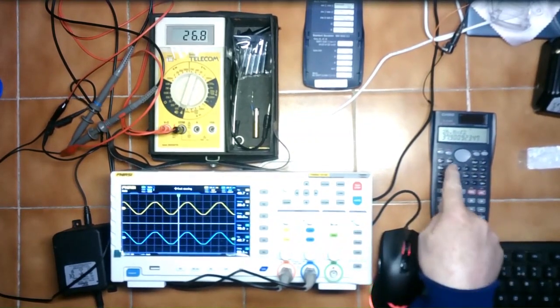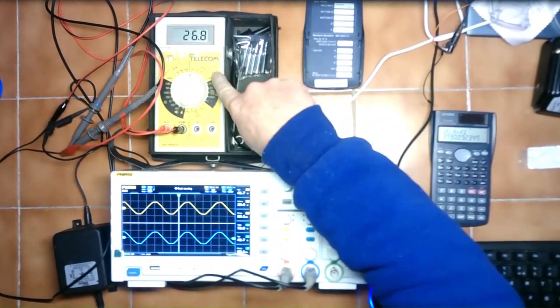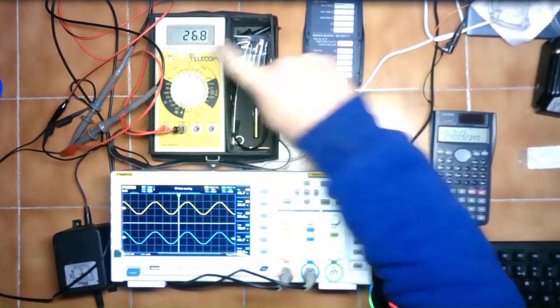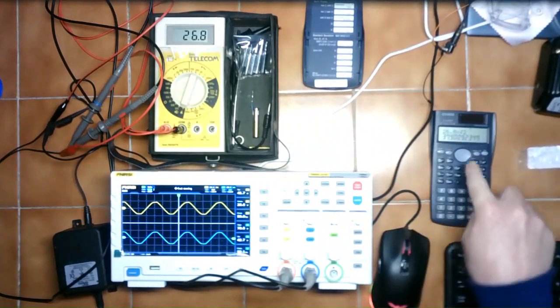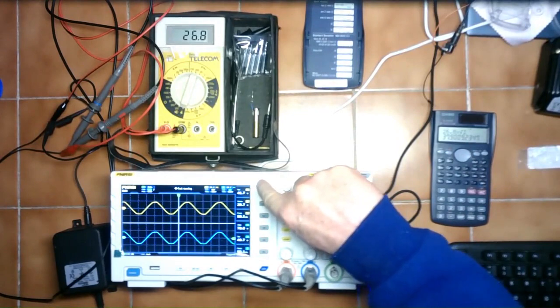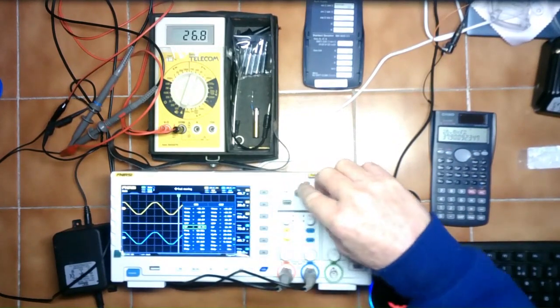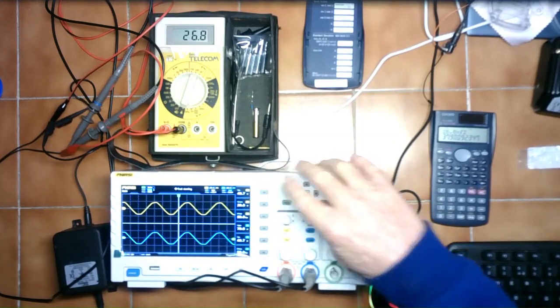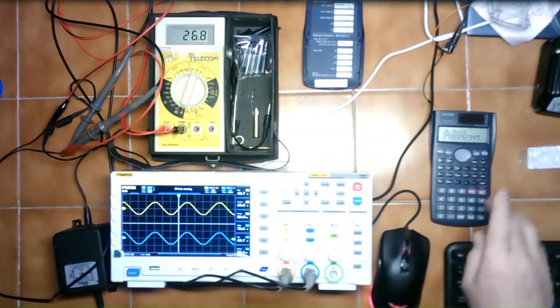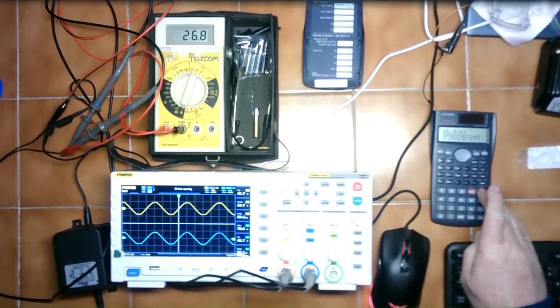So now you can see what the value should be, if we take this as the actual more accurate reference, 26.8 would have a peak of actually 37.9 and it's actually telling the unit saying it's got a peak value of 40.7. So the difference 40.7 to 37.9 is 2.8 volts. That's the error.